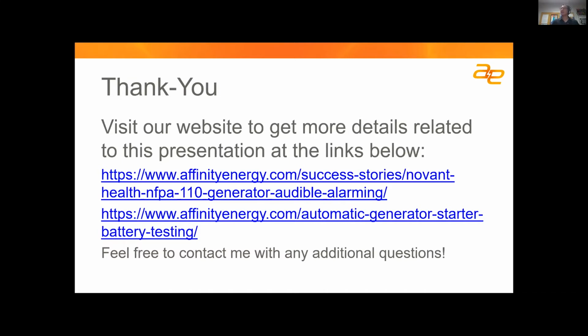In all cases I'm aware of, we've been utilizing the hospital's network, typically the building automation network. There are some smaller implementations where the control or annunciator panel is very close to the generator and we've just done a dedicated solution, but we've not put in anything like a ring to mitigate loss of communication. That might be something to explore, but it hasn't come up. We've not had too many issues related to that.